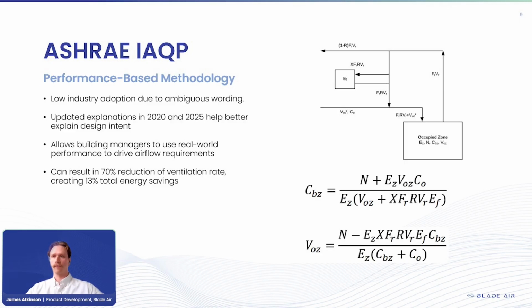So you can reduce your outdoor air fraction so that you're not having to treat as much fresh air, and then you get the associated energy savings. In 2025, ASHRAE released a calculator where you can plug in your variables, your different zones and the expected uses, and track what you expect your new ventilation requirements to be. There's a variety of different results, but commonly you'll see a 50 to 70% reduction in your ventilation, right? So you're still providing a similar amount of air volume to the space, but the fresh air is highly reduced because we have much better air cleaning technologies now. And these are things that can be implemented quite simply without a huge retrofit.